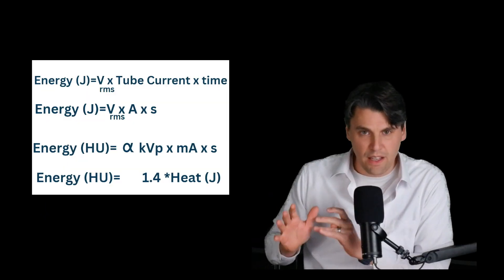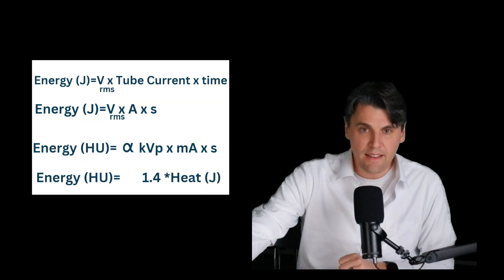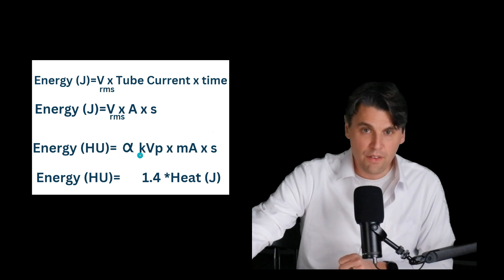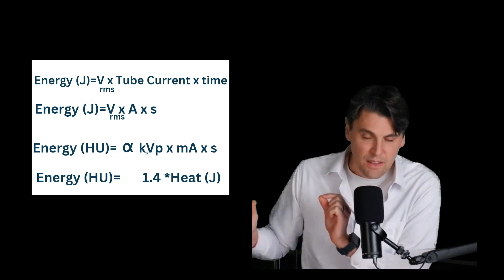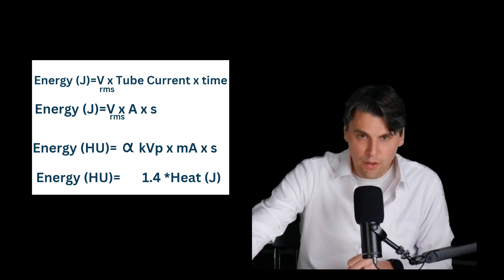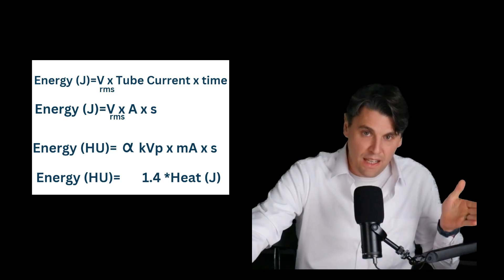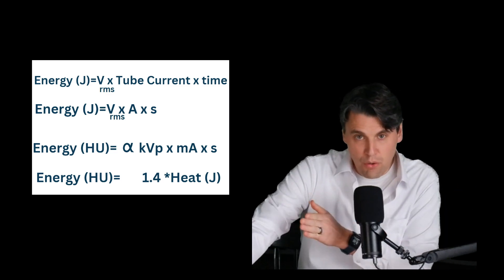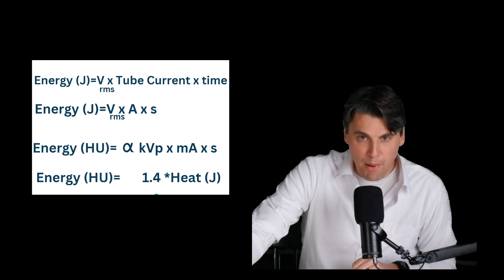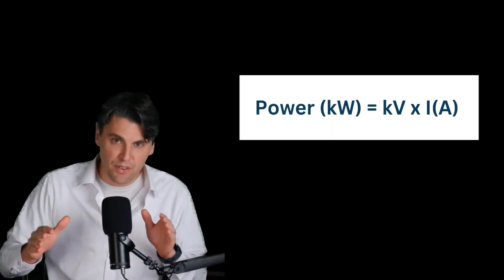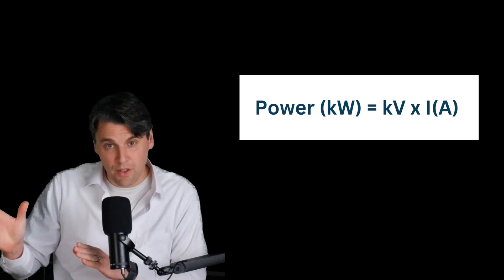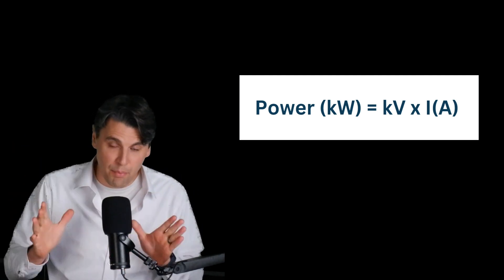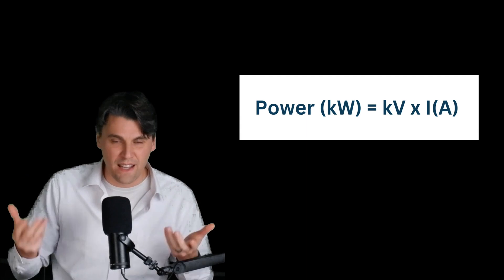To convert between these two units, for the case of a perfect, nice flat KVP, the factor is basically 1.4. So the conversion from energy in joules to energy in heat units is to multiply by 1.4. Power is just that energy divided by the time — kilovolts times the current gives you the power in kilowatts.